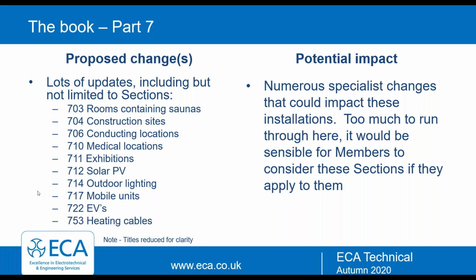Often these things are recommended or required by manufacturers for certain devices. Some of the new 3-phase washing machines - okay, they're working on a single phase, but they're using 3-phase motors, I can't remember the make, I think they might be one of the more expensive ones - specify in their installation guide or manual that they should be protected by an RCD type F. And also with EV charging equipment, EVCE etc, they do specify the types of RCDs that should be used.